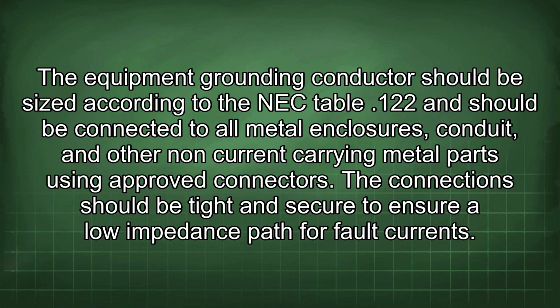The equipment grounding conductor should be sized according to the NEC table 122 and should be connected to all metal enclosures, conduit, and other non-current carrying metal parts using approved connectors. The connection should be tight and secure to ensure a low impedance path for fault currents.